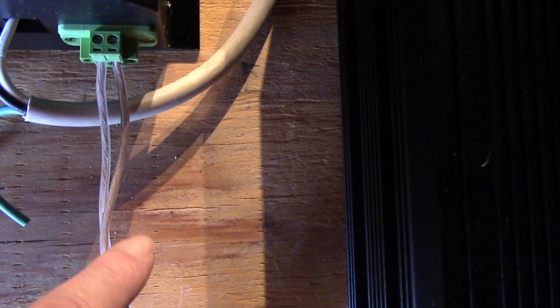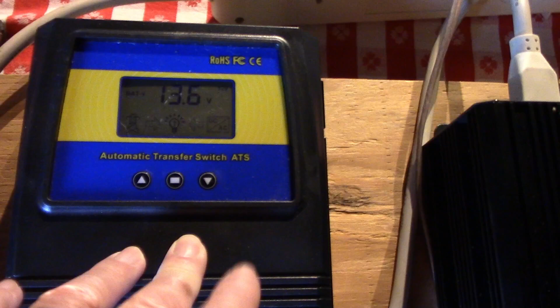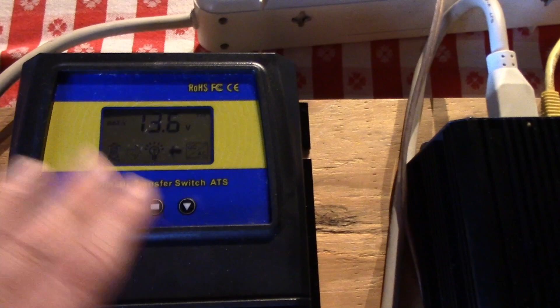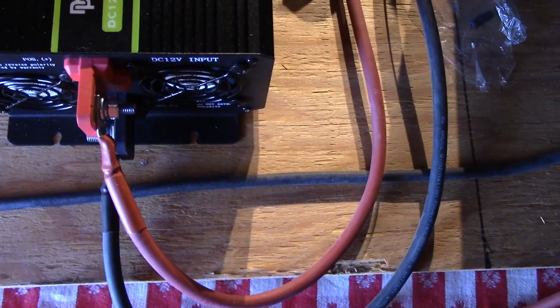So the next device that we have is the automatic transfer switch. This side is plugged into the utility power. This side goes to a power strip here to distribute power. And this side plugs into the inverter, which is right here. And then these wires here go back to the battery. So this thing can monitor the battery voltage, and when the battery voltage falls below a certain point, it'll switch over from battery and solar over to grid power, which is right here. It does that automatically, and you can set the beep bop boops, and you can get the correct voltages in there to where it transfers.